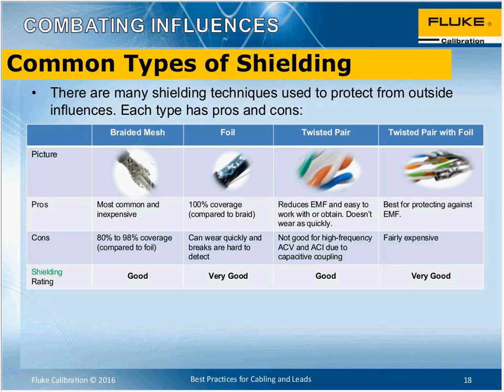Now, in here, you'll see we've put some pros and cons and some ratings for the type of shield and the effect of shielding. Like most things in metrology, there are no absolute rights and wrongs. When we're talking about shielding rating here, it's a rule of thumb: how much shielding, and is it good from an electrostatic point of view, is it good from a magnetic point of view? Clearly, those foils and braids are really a Faraday cage, so that's good for electrostatic, either static electric fields or varying electric fields. And to make a very tight loop, in other words, to have 2 conductors running together, either very close side by side, concentrically in a coaxial connector, or in a twisted pair, helps us with the magnetic shielding. So you can see there, most of those cables are pretty good, and some are better than others for electric versus magnetic.